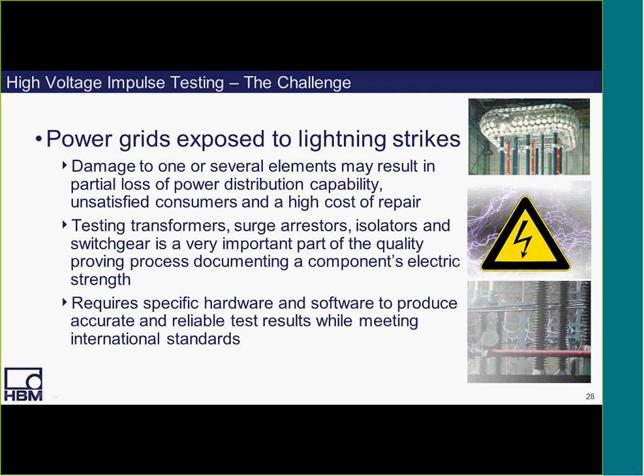Now we're going to move over to the high voltage impulse testing application. And here we have power grids that are exposed to lightning strikes. In fact, damage to one or several elements may even result in partial loss of power distribution capability, unsatisfied customers, and even a high cost of repair. So you can imagine it's quite important for testing transformers, surge arrestors, isolators, and switchgear, because it's part of the quality proving process documenting a component's electric strength.